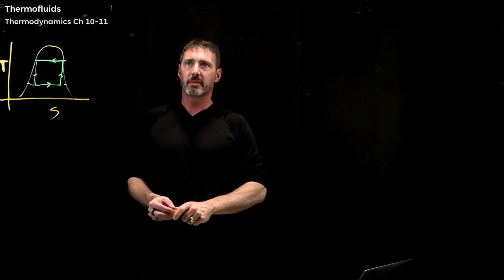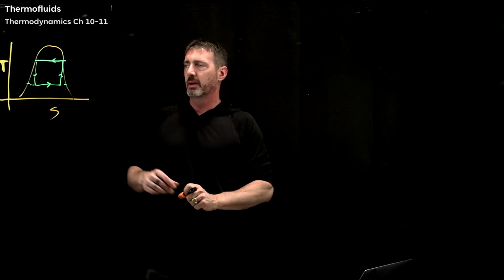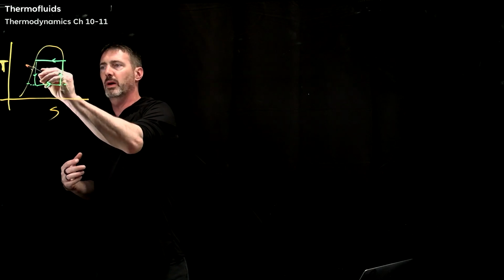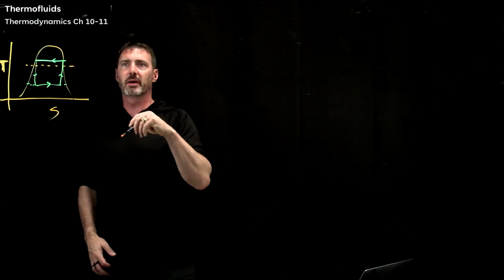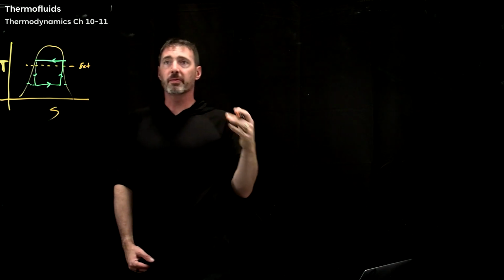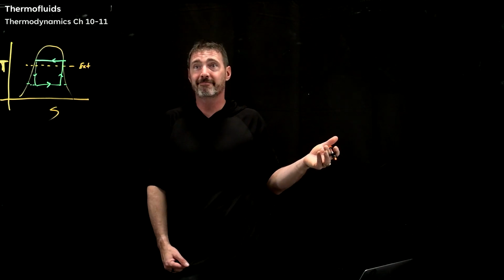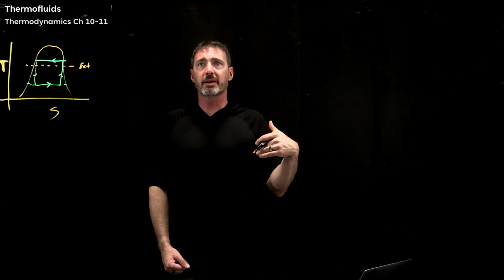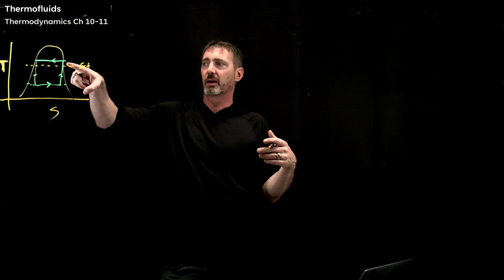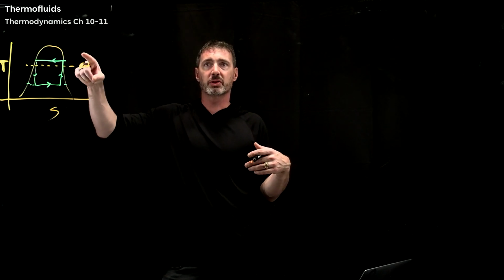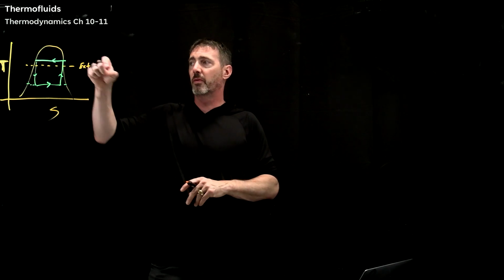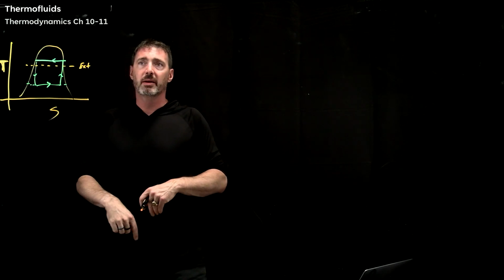This is true for a fridge too. This part of the loop, the coil in that refrigeration system, is well above whatever your external is. If it's a fridge, external is your kitchen. If this is an air conditioner, external is the outside. Even if it's 100 degrees here in Texas, the temperature of this loop once pressurized is 120, 140, so there's room for it to exchange heat with the outside.